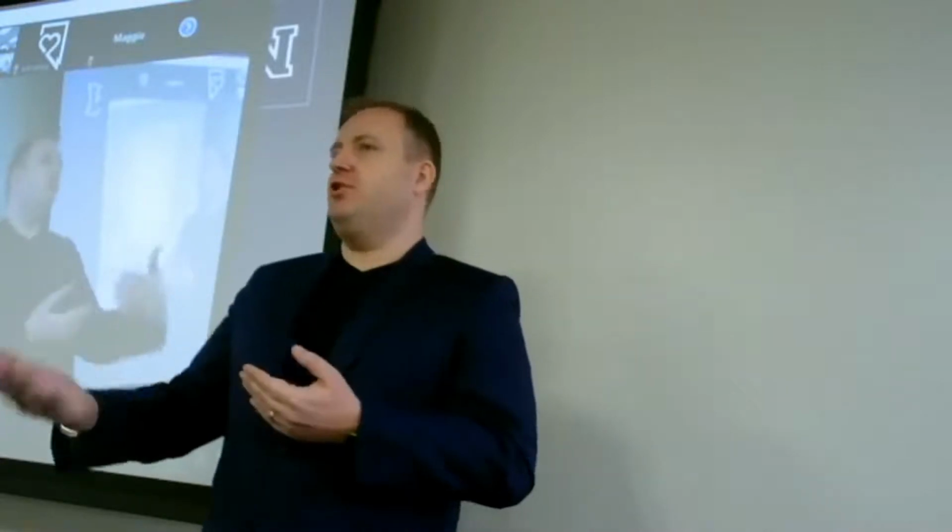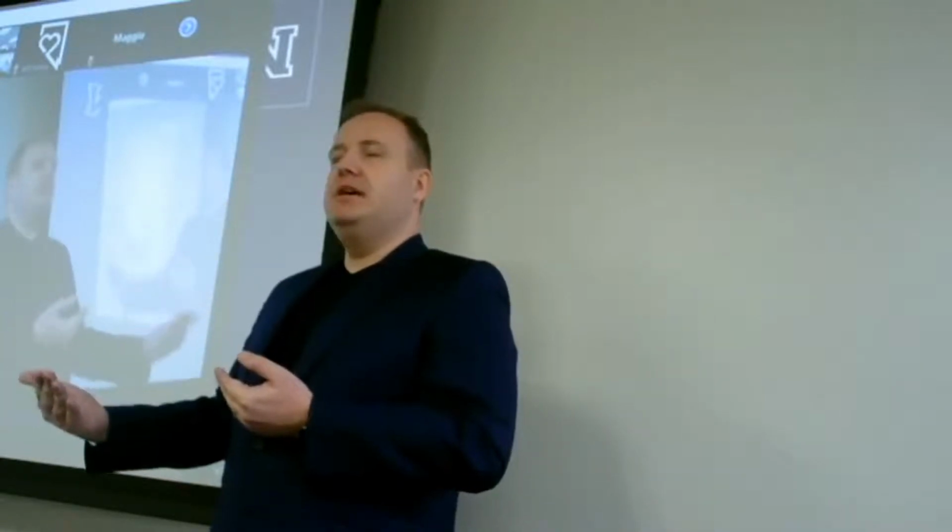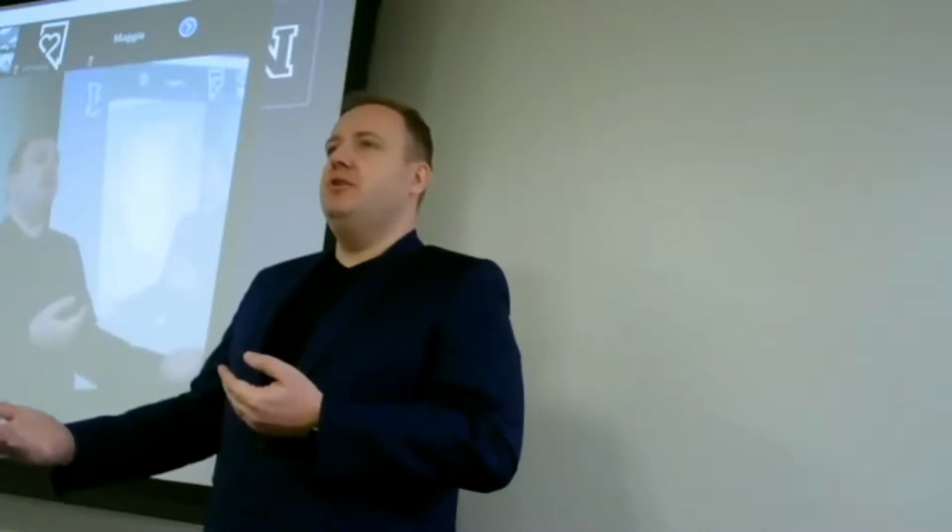Mostly we work with imaging devices, so CTs, MRIs, C-arms, small dental X-rays, and this is what we focus on. So we ensure the quality of the image, not the dose, whether you get the correct dose during the procedure, but whether the image that the device produces is of diagnostic quality. If you go for mammography, it won't miss this small tumor in the breast, and it will save your life. Big machines in the medical center, yeah.